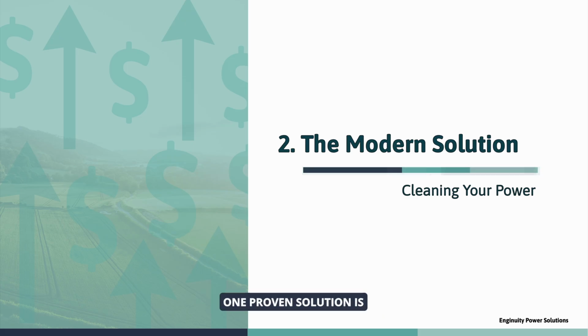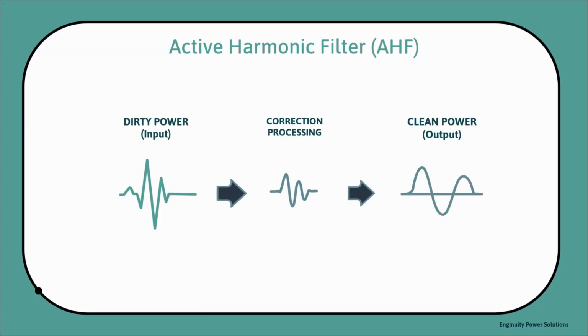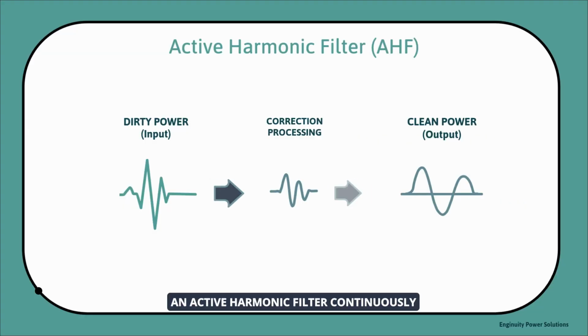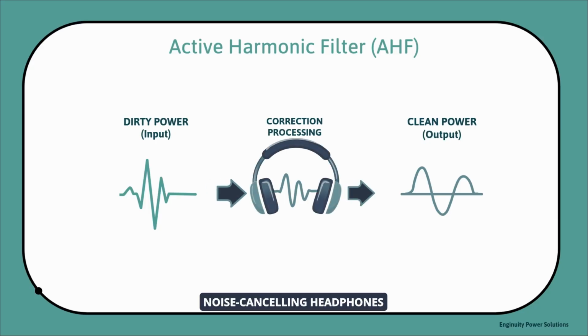One proven solution is the Active Harmonic Filter. An active harmonic filter continuously monitors your electrical waveform. It detects distortion in real time. It then injects an equal and opposite current to cancel that distortion. The effect is similar in principle to noise-cancelling headphones, but applied at an industrial power systems level.